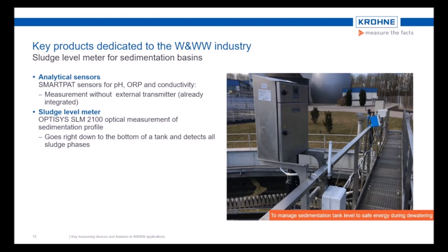Another device belonging to the analytical product portfolio is the sludge level meter to measure and manage the sedimentation tank level. In contrast to the widely used ultrasonic principle, the SLM 2100 uses an optical sensor that is immersed into the medium to measure the concentration of the suspended solids at different depths. The sensor travels up and down through the medium, continuously monitoring the local concentration of suspended solids.